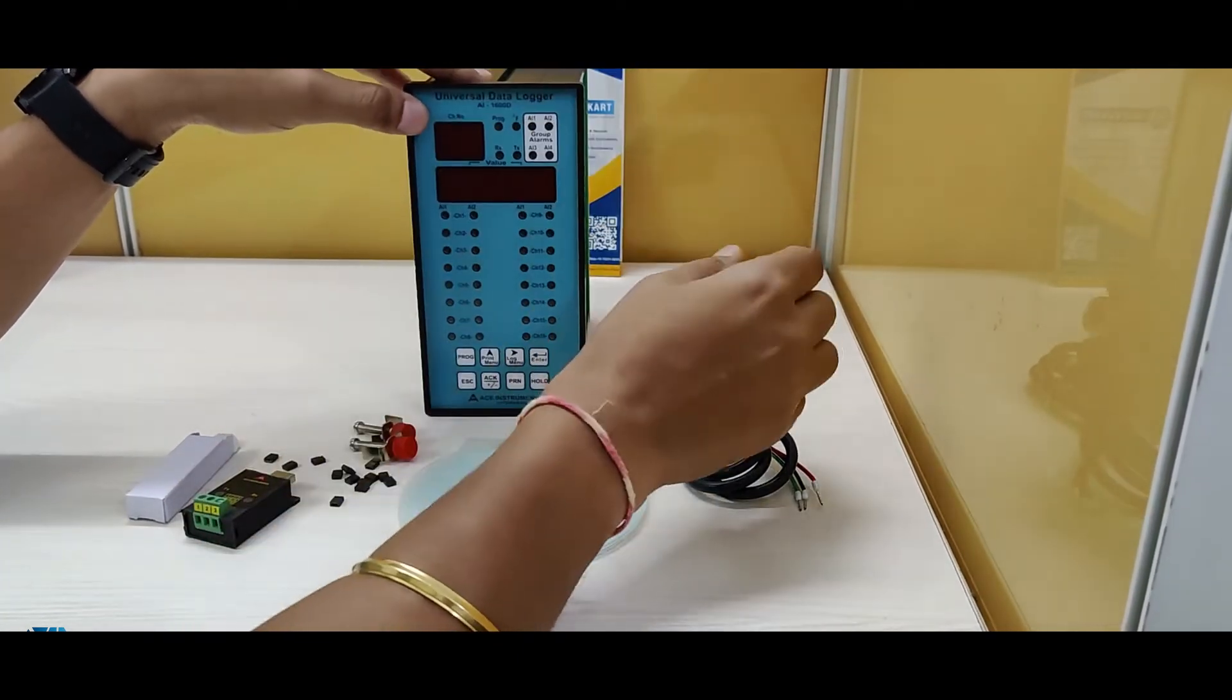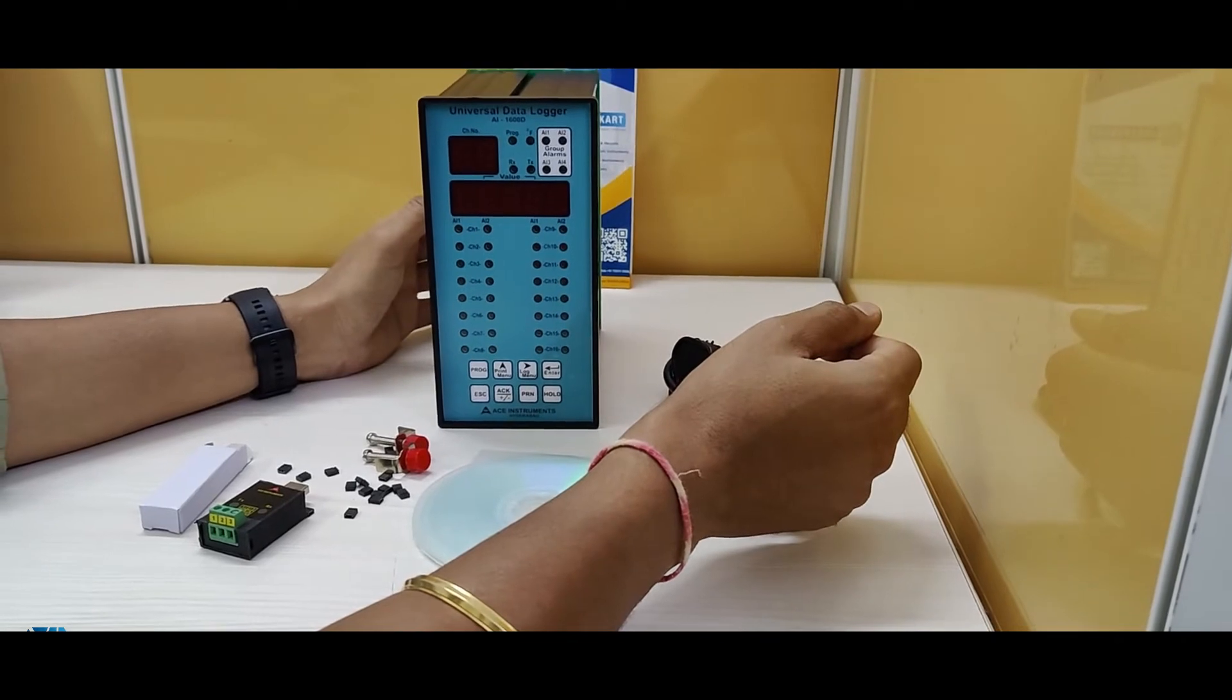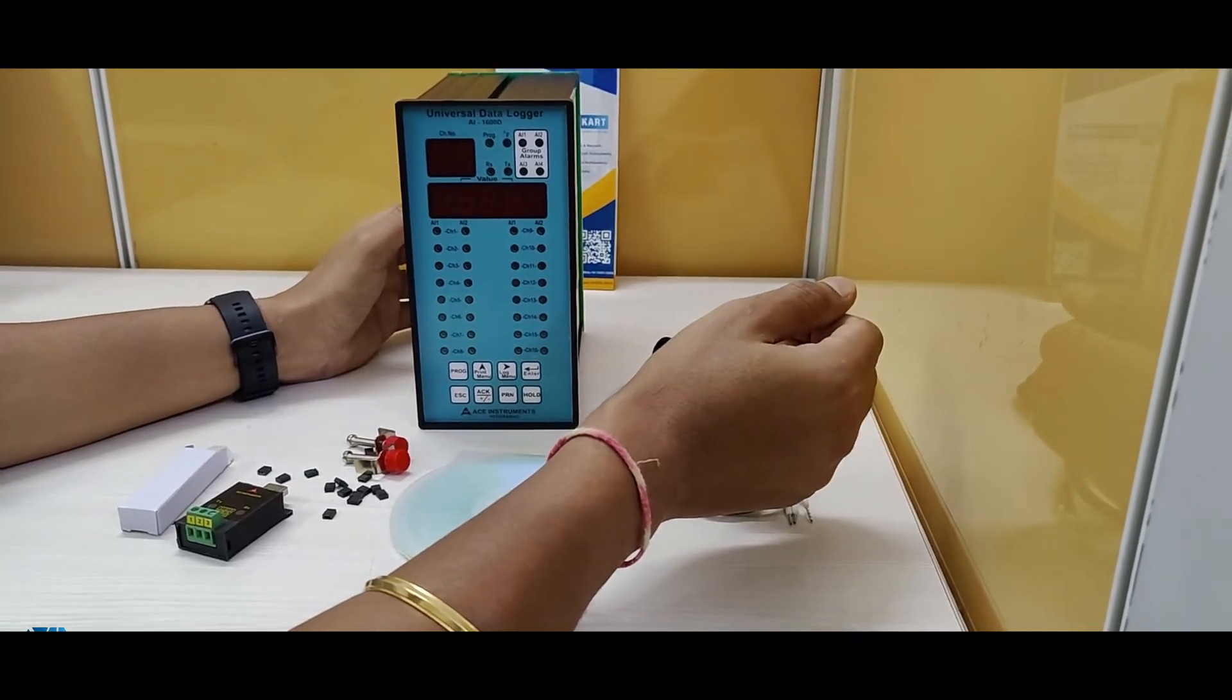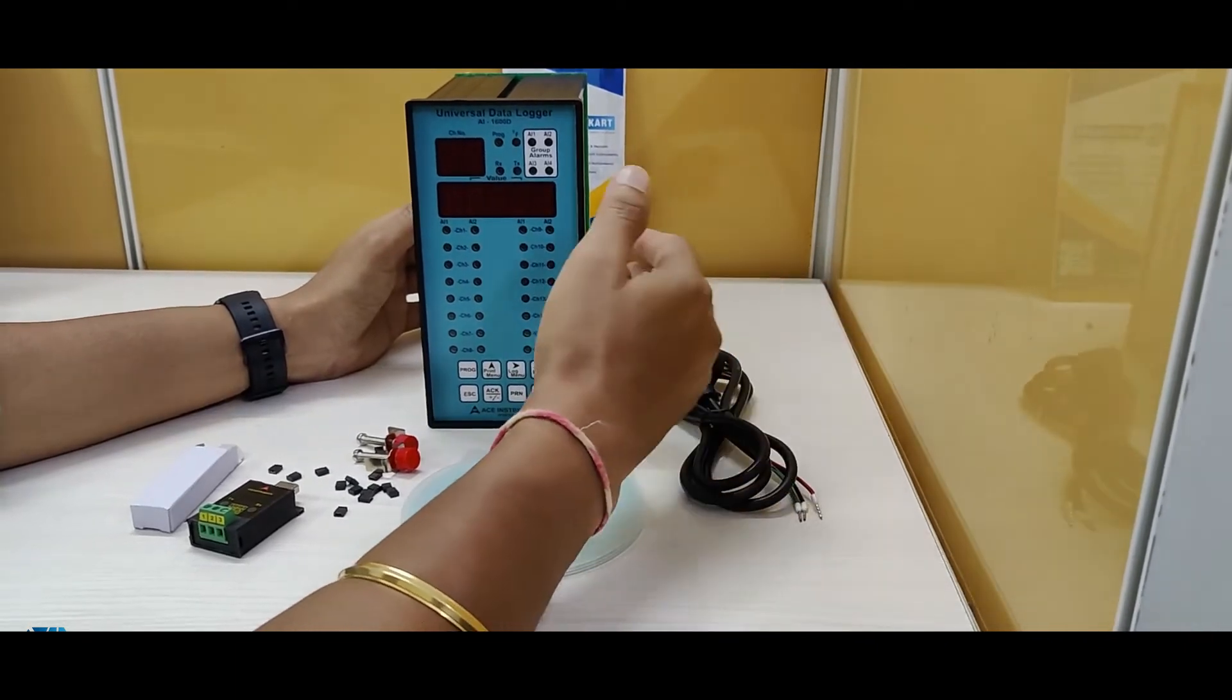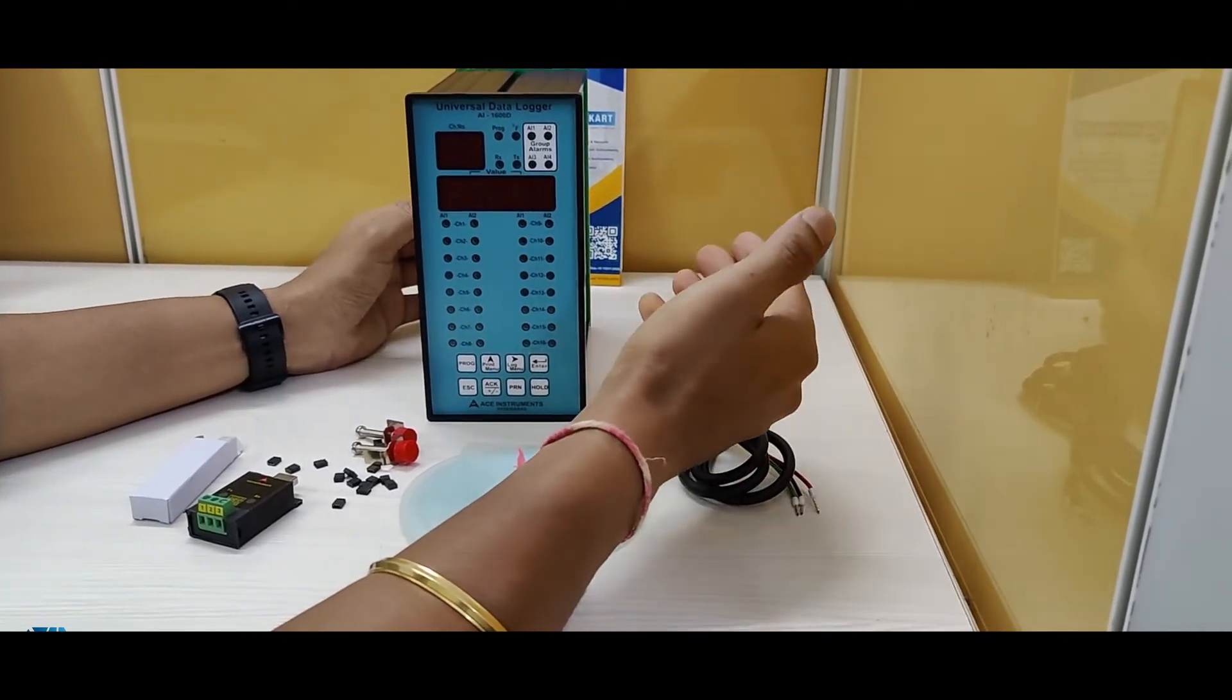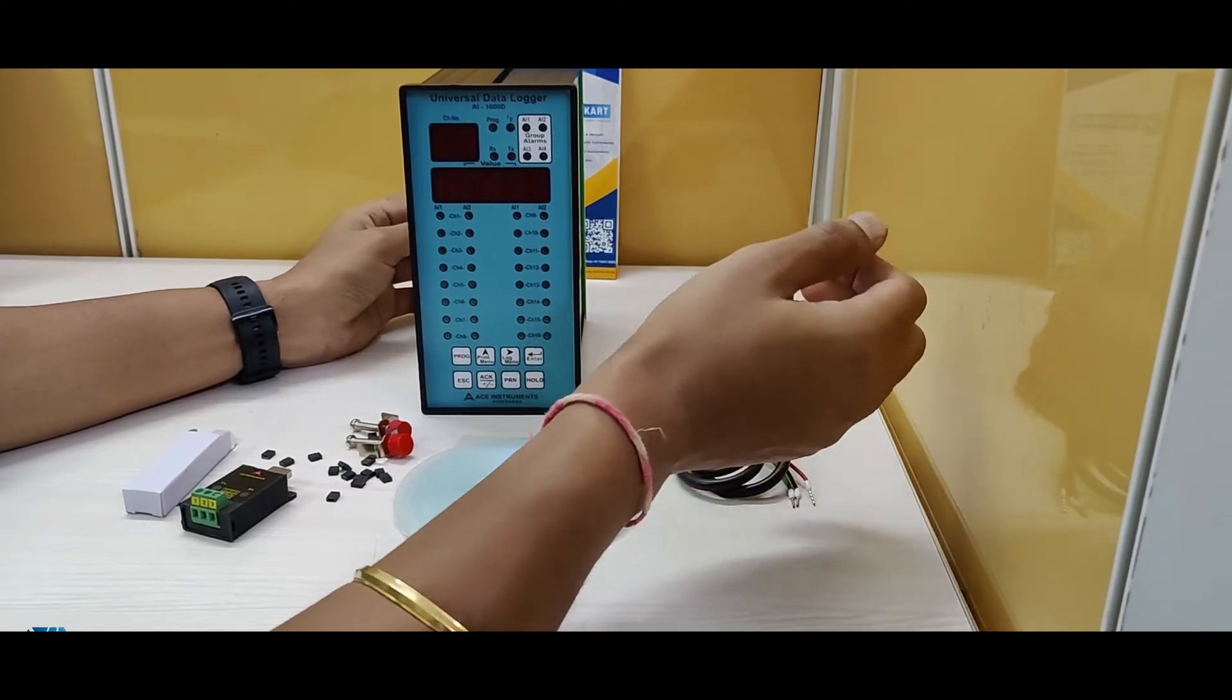Now there are two kinds of software which are available along with this data logger. One software which is 21 CFR compliant, which means that it is having a multi-level security so that no one can tamper the data, and other software which is a standard software connected to the PC just to see the temperature or whatever parameter is connected in a graphical or tabular manner where you can analyze this data.